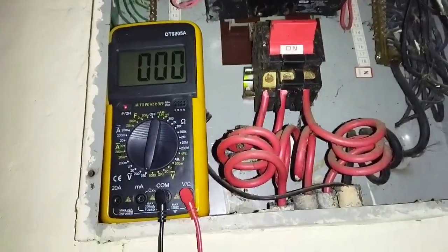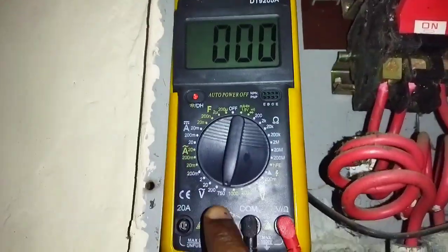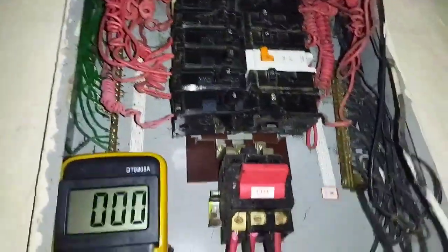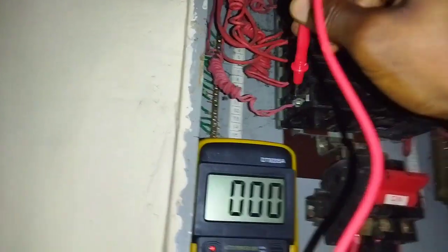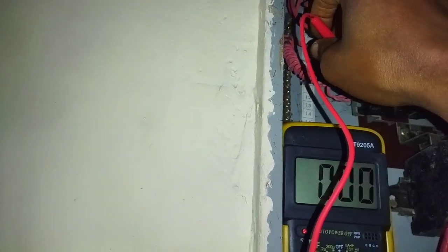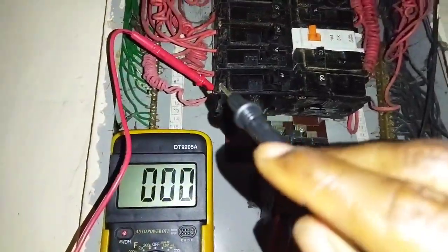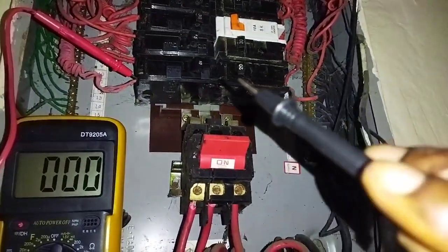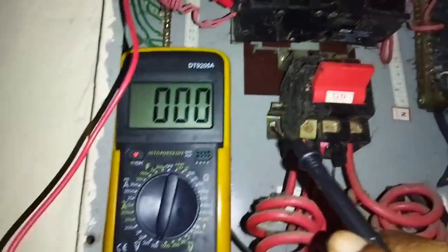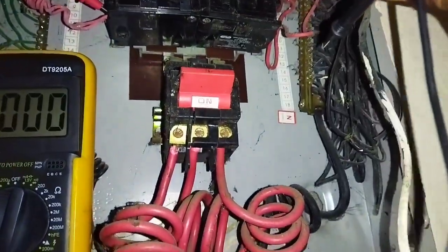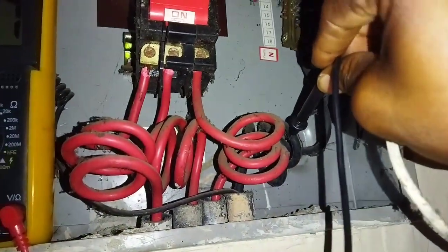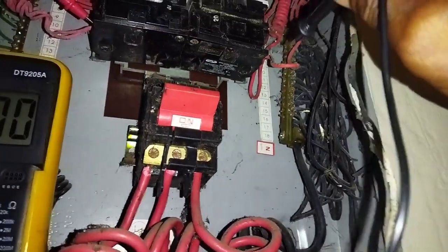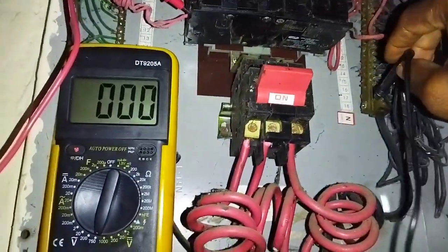Okay guys, this is our digital multimeter set to AC voltage 750 volts. We are going to see how to test for a faulty circuit breaker. I'll place this probe here. Then this is the neutral link. This probe is at the output of the circuit breaker. If the circuit breaker is in order, I should get some voltage reading when I test for voltage across this terminal and the neutral link. This is the neutral from the control, and this is the neutral link. The neutral is the same for all the loads. So let's see what happens.